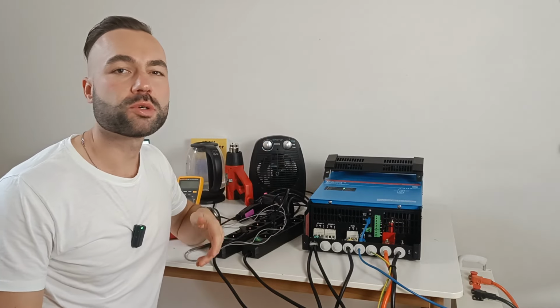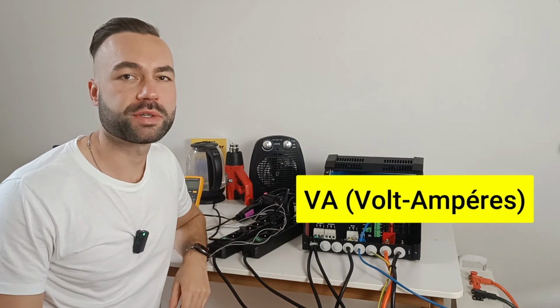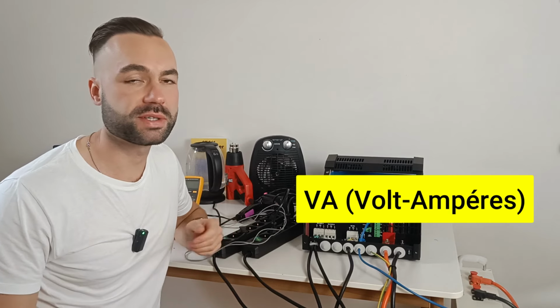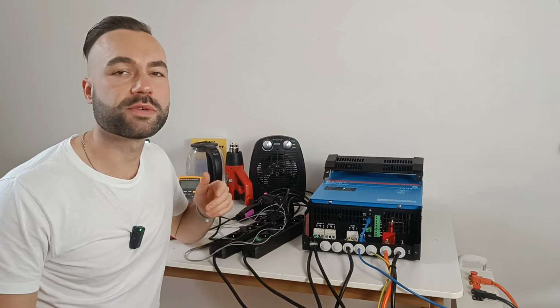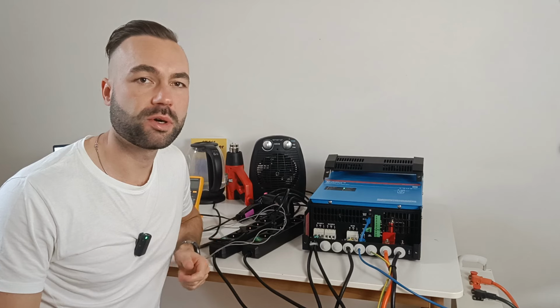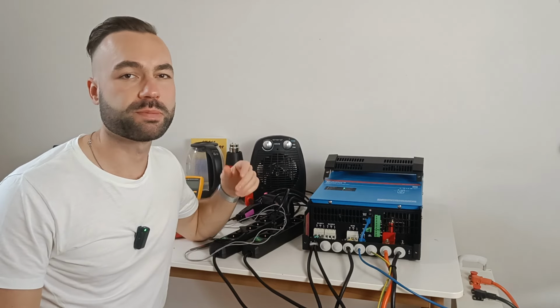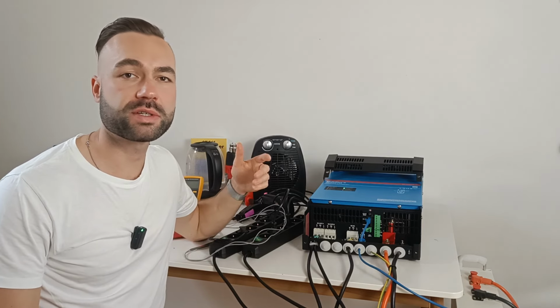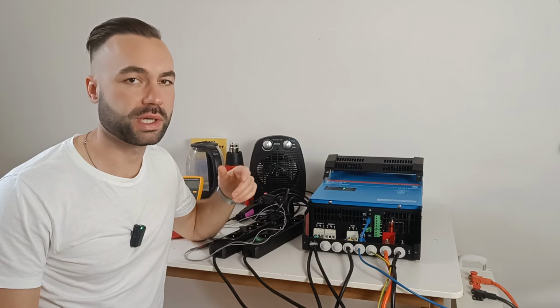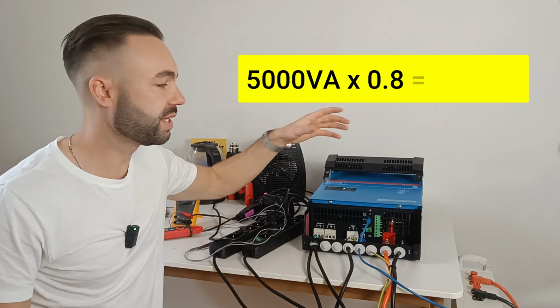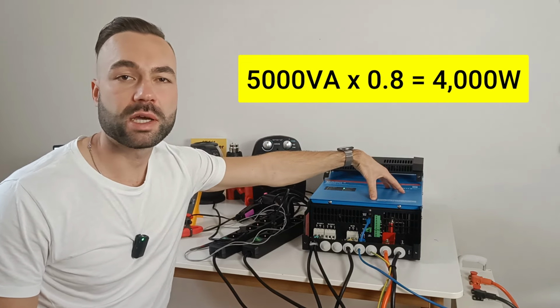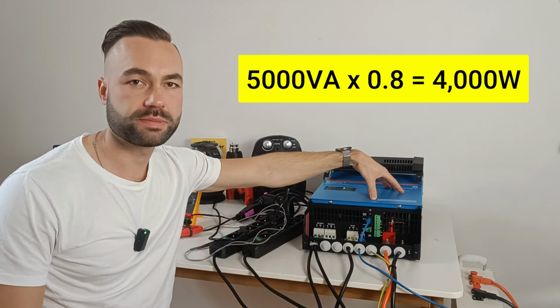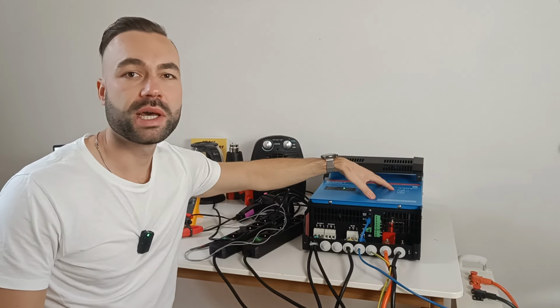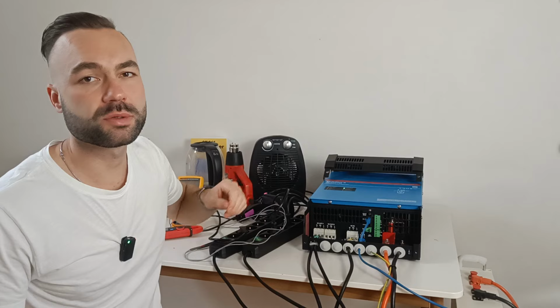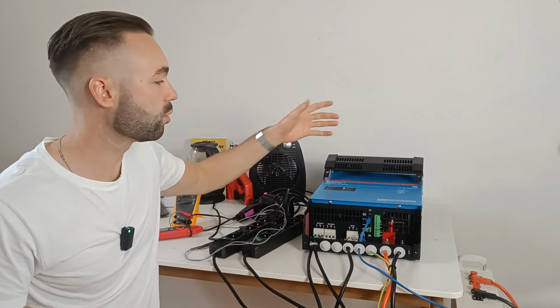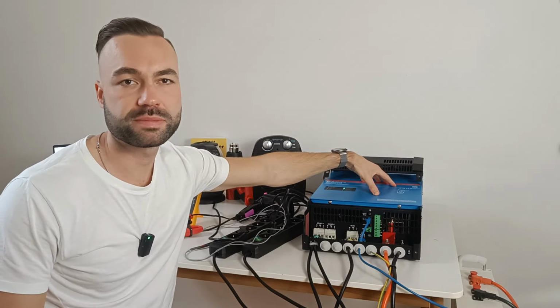Victron products show their power in volt-amperes, or VA, rather than watts. VA accounts for both voltage and current, while watts reflect actual power use. If your appliances have a power factor of 0.8, then a 5000 VA inverter is roughly equivalent to 4000 watts. This MultiPlus can handle peaks of 9000 watts because of its low frequency inverter inside.